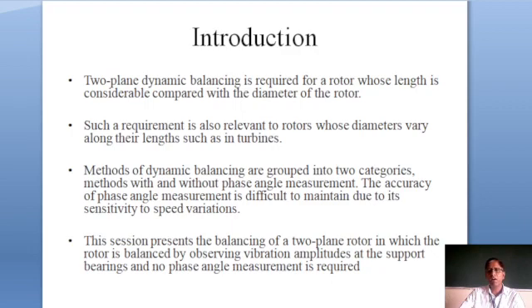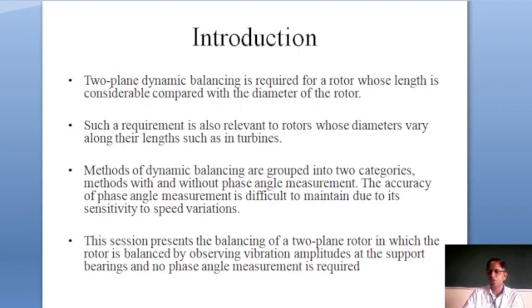A two-plane dynamic balancing is required for a rotor whose length is considerable as compared to the diameter of the rotor — when the length of the rotor is very large as compared to the diameter. For such a rotor you cannot apply single plane balancing or static balancing, because at both ends of the rotor a couple is developed, and such problems must be handled dynamically rather than statically. This is the multi-plane balancing method.